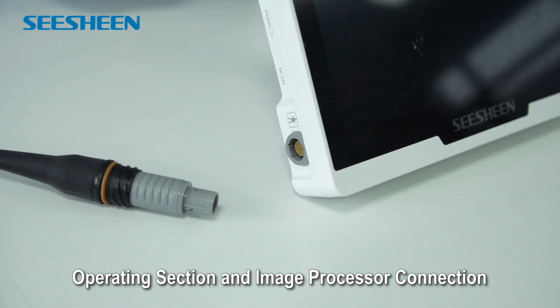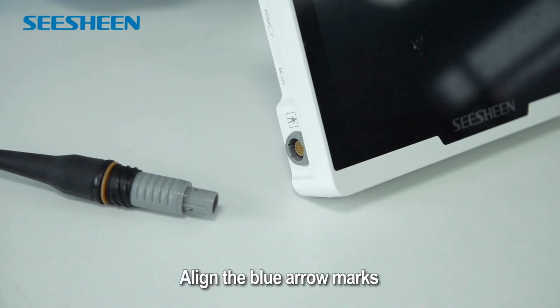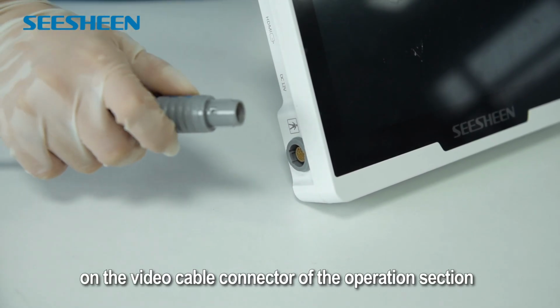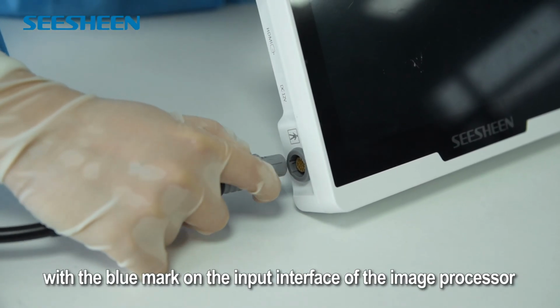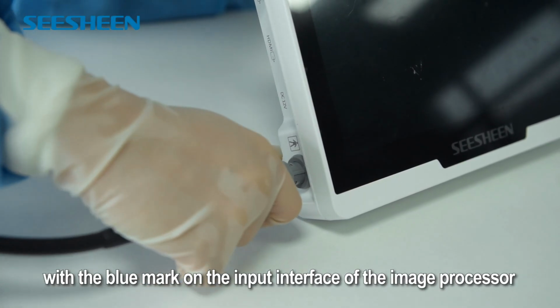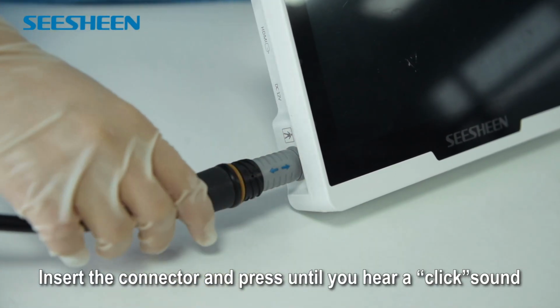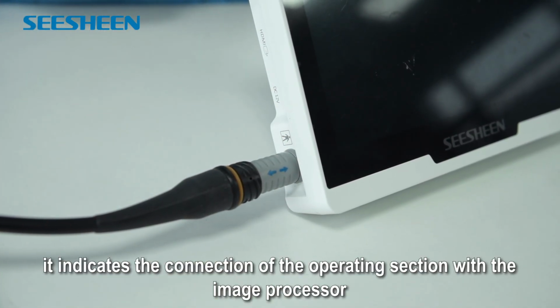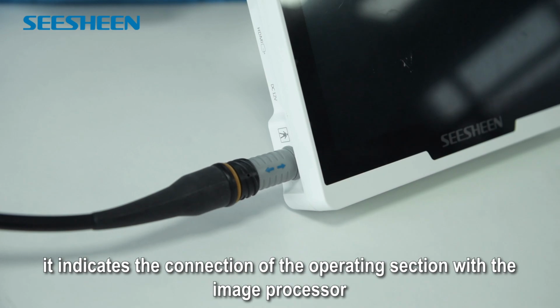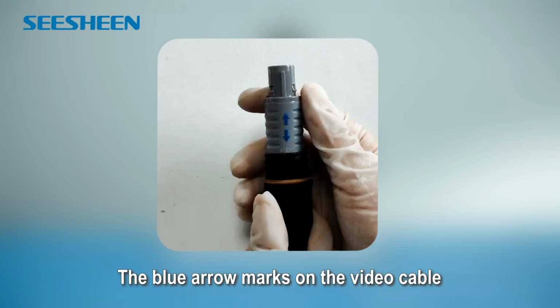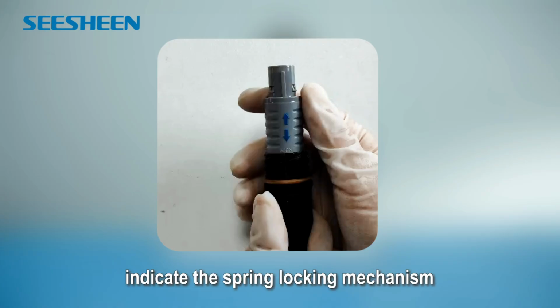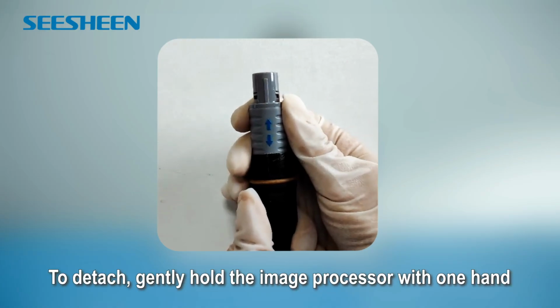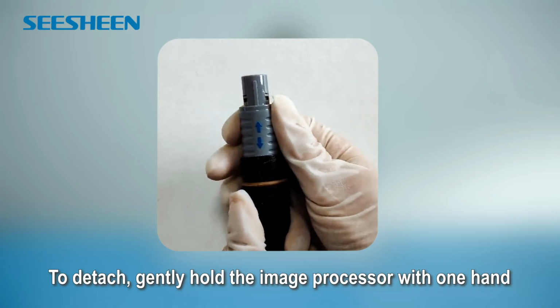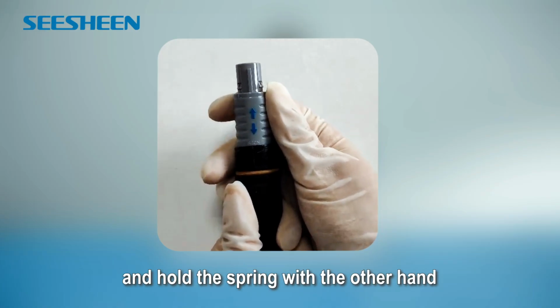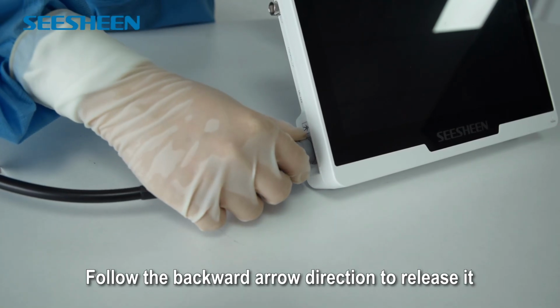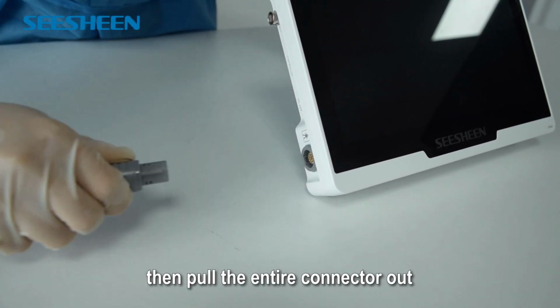Operating section and image processor connection. Align the blue arrow marks on the video cable connector of the operation section with the blue mark on the input interface of the image processor. Insert the connector and press until you hear a click sound. It indicates the connection of the operating section with the image processor. The blue arrow marks on the video cable indicate the spring locking mechanism. To detach, gently hold the image processor with one hand, and hold the spring with the other hand. Follow the backward arrow direction to release it, then pull the entire connector out.